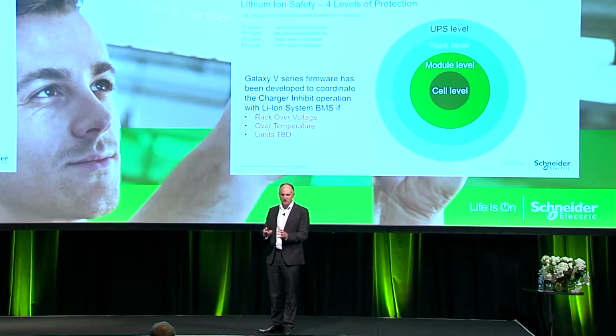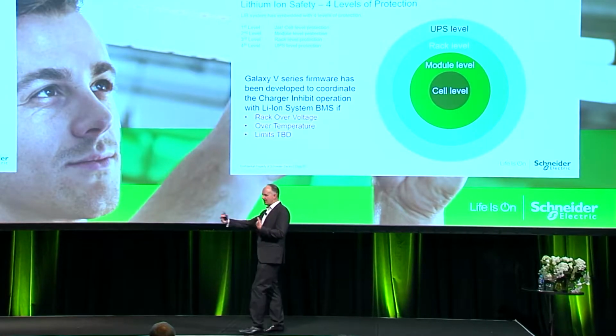So that's the cell composition itself. We go one step further - the cell itself has a huge amount of protective mechanism. The module they're connected together in has a next level of protective mechanism. Then at the rack level, there's a full-blown battery management system built in with the lithium-ion - not a battery monitoring system, which typically just monitors the voltage of the battery. This thing's a battery management system. It's able to look at individual batteries and cells, triage things, make sure you get optimum life out of it, and provide a lot of intelligence, including communicating with the UPS.